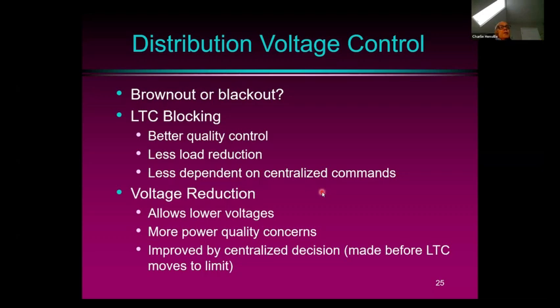Whereas if you use voltage reduction, which is another method of reducing the demand of the load, this allows lower voltages, but you have to worry about your power quality. And your centralized control devices will know better whether the system really is in trouble and whether you should reduce the voltage at certain locations to try and reduce your load a little bit. I should mention this business of reducing voltage is quite complicated, because if you reduce it above or upstream of your load tap changers, as you reduce the transmission voltage, the load tap changer is going to just increase the voltage to your load delivery points, and you won't do any good. So you have to try and control your voltage below, or downstream of, your load tap changers or your voltage control devices.